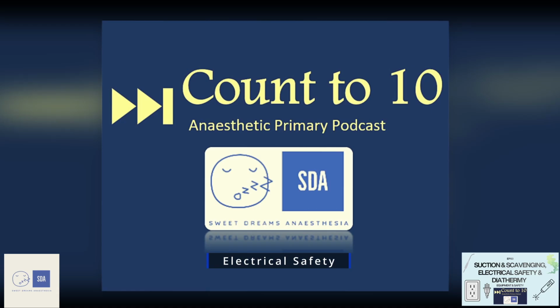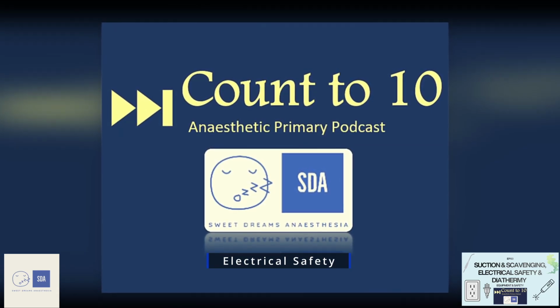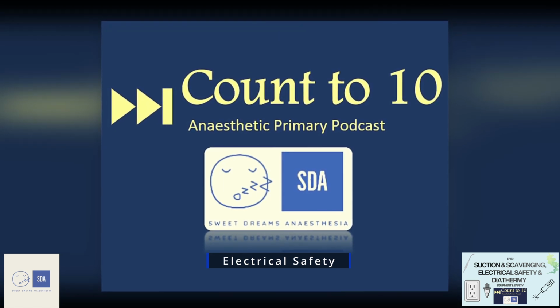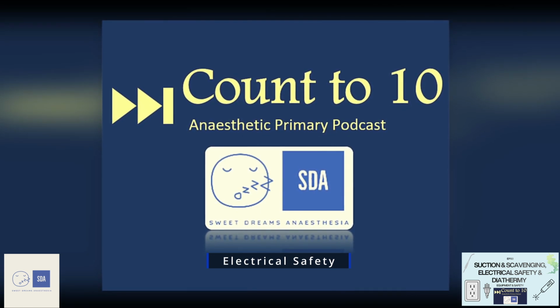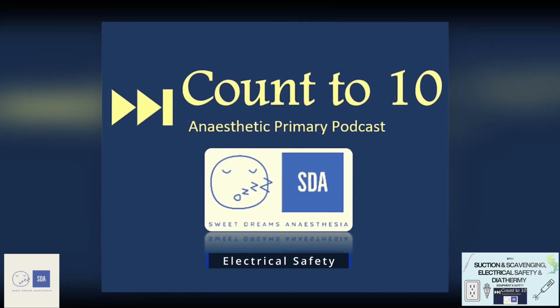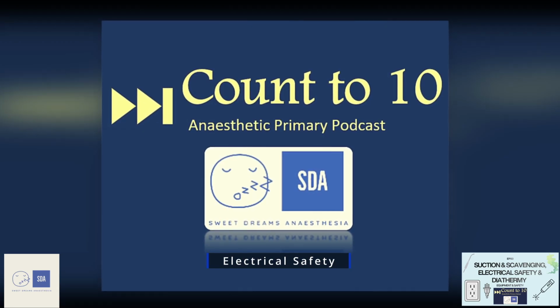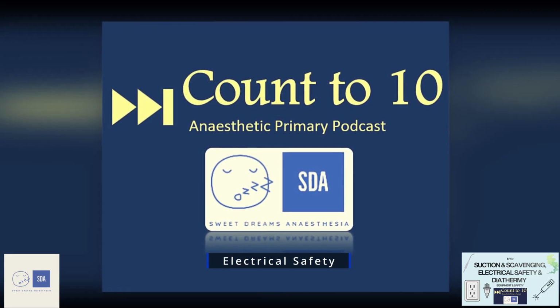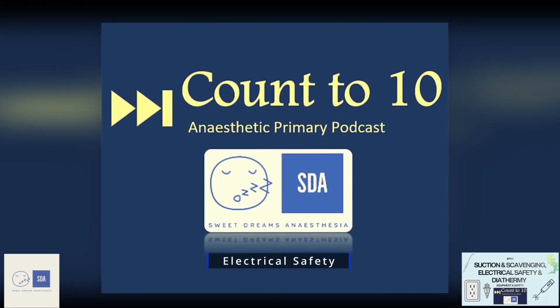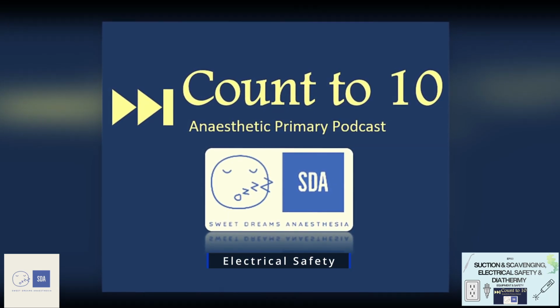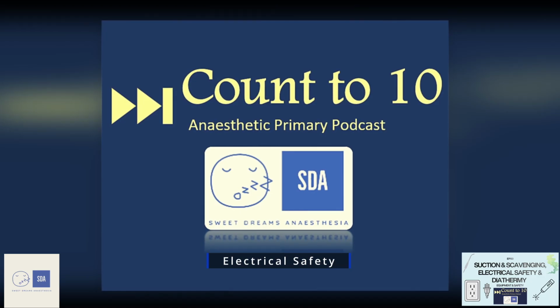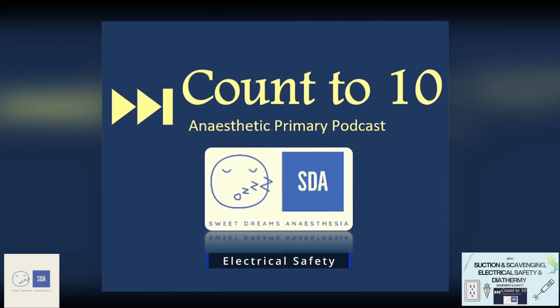So then what do we do in the theatre environment to decrease the risk of these types of electrocutions occurring to ourselves or to the patient? Well, there's some really simple things that we do as part of electrical safety, such as insulating the wires so that they have a high resistance substance around them, decreasing the risk of you touching an active wire and then being part of that path of least resistance. There's fuses that will cease current flow if there's a high current that exceeds a certain threshold, and these are the same as the fuses that you have at home.